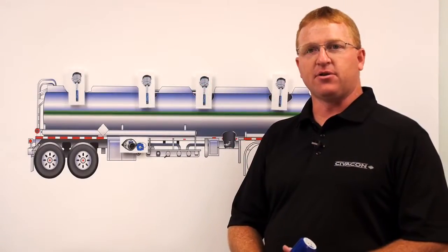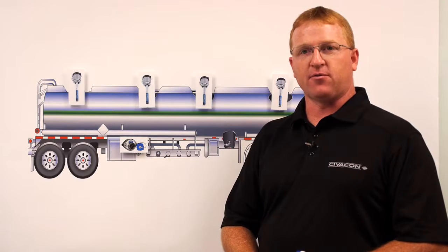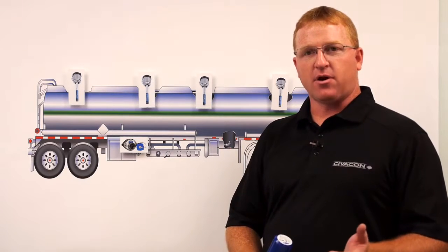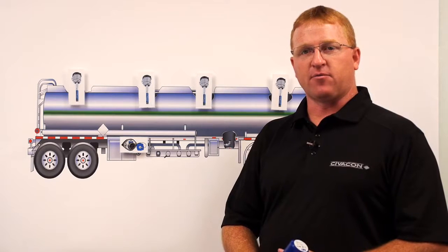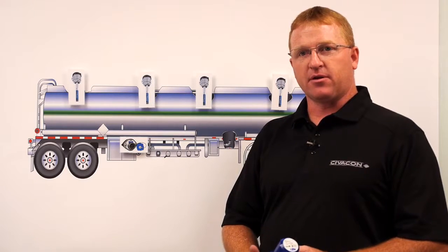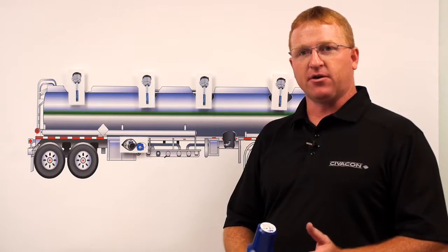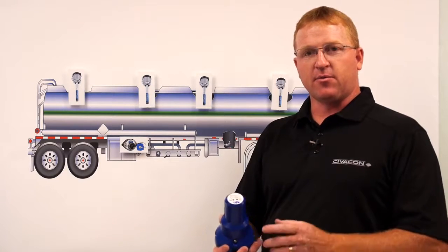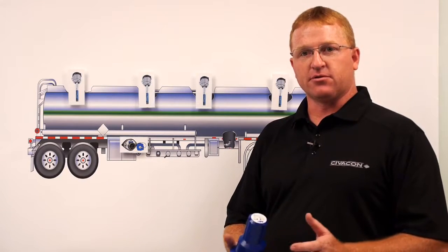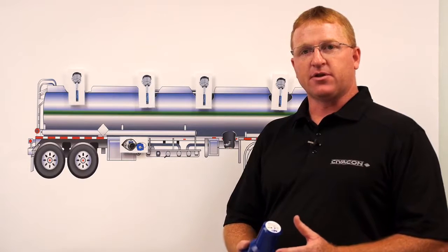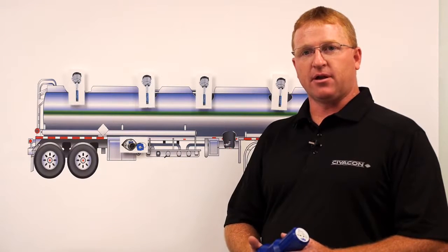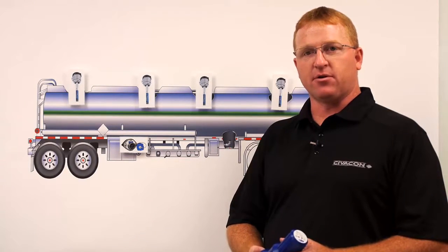That completes the troubleshooting of 2 issues that are commonly found on a 5-wire overfill system: wiring problems and a defective probe. A third problem that is commonly found is in the grounding circuit. That can be determined if your tester shows that there's a fault in the ground system. We have an extensive video on this at Civacon.com that explains how to troubleshoot the ground circuit. This concludes our troubleshooting of the 5-wire overfill systems and the 3 issues that are most commonly found.